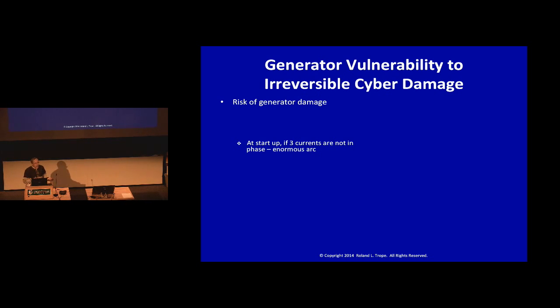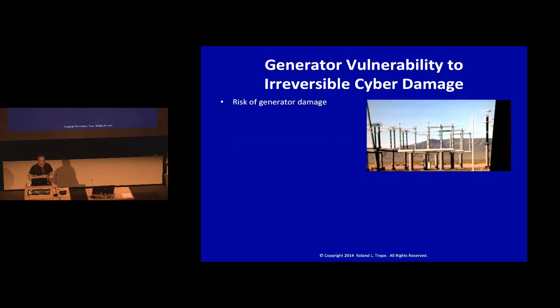This would be particularly problematic if you've had a generation plant offline for maintenance, and then at startup, if you don't have those three currents in phase, you could have an enormous arc. Now, when I say an enormous arc, I want to make sure that everybody understands how large these things can be and how sustained. They're not just one instant, a quick spark.